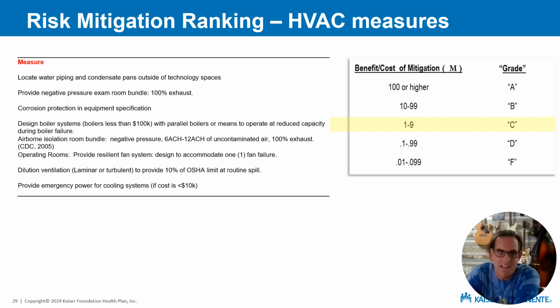Again, that is not N+1. That is reduced capacity during 1 failure. And when we say $100,000, that's the boiler, the pad, the piping, and all the controls. So dual boilers is a marginal investment so long as the boilers are kept inexpensive. You'll notice airborne isolation rooms is on this list. Why isn't that an A or a B, you might ask? It's a very confident mitigation, but it's also a very expensive one.